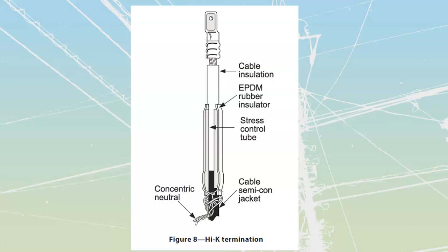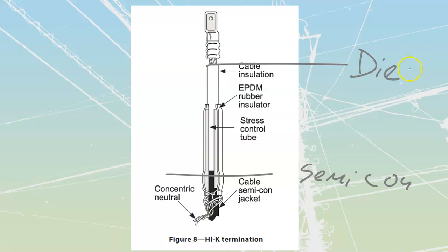Same deal, I'm going to use the manufacturer's guidelines. They're going to tell me how far I'm going to strip everything back on this cable. Once I've got everything stripped back, that's where my semicon, or insulation shield, ends. This is where my dielectric ends over here.